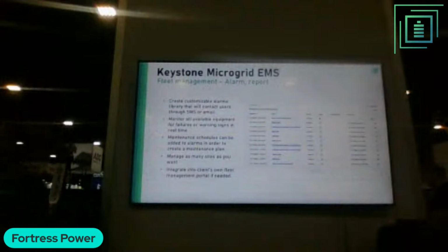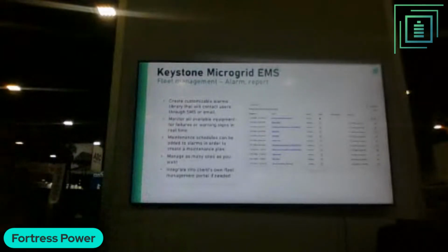Last but not least, our fleet management alarm screen—not just our equipment, right? Anything with a Modbus map we can integrate into our system. Whether it's a PV inverter, a genset, an energy meter, geothermal, wind turbine, you name it. If it has a Modbus map and can send and receive signals, we can feed the alarms to our microgrid control system and send it to the cloud so you can see it in one place.